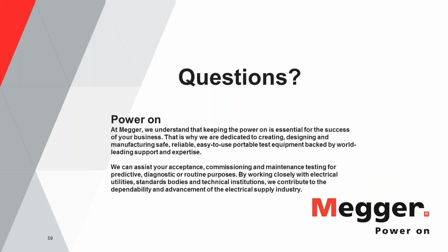Okay, I guess Sanket appropriately answered that question. I just want to add one more point to that question: what the question is asking is something that is being done out in the field all the time, because the amount of current that you can get from any given instrument may not be enough for you to test at the trip settings of that breaker.